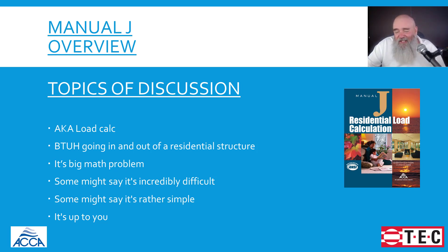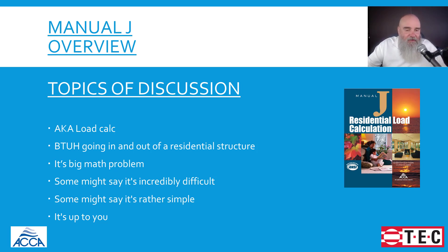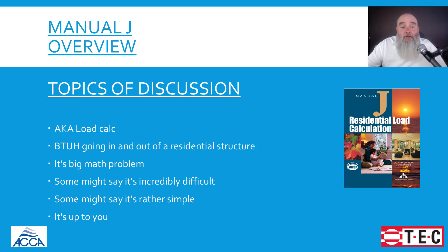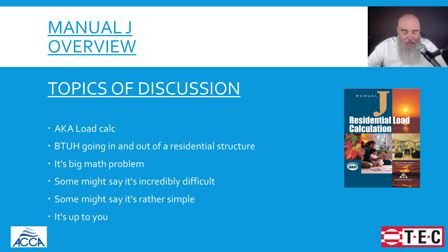Some people will tell us that it's incredibly difficult to calculate these loads, and then there are others who say it's fairly simple. I'm kind of in the middle. If you do your due diligence and put some effort into it, it's not easy, but it's not difficult. As the last bullet point says, it's up to you. You can make things harder than they actually are, and some of the stuff that makes it too easy — I don't know if you want to follow those. I'm not a big advocate of things like square footage per ton or rules of thumb, but you can also use square footage per ton as a ruler, if you will. There are times we can look at what our software is telling us our square footage per ton is and compare that to similar houses and similar structures. That's a good way to use rules of thumb.